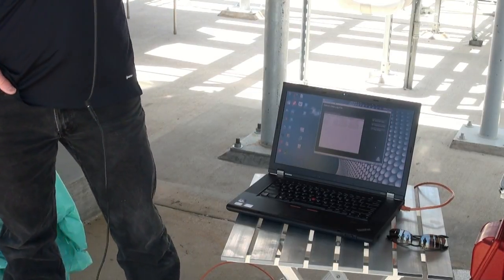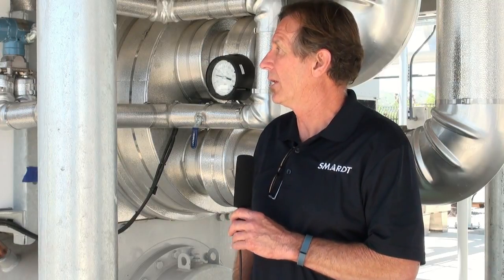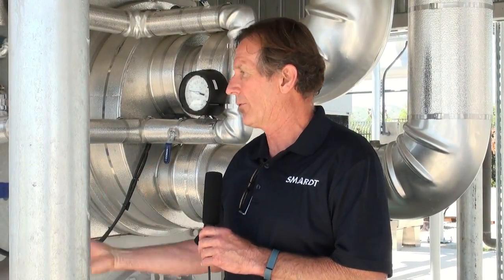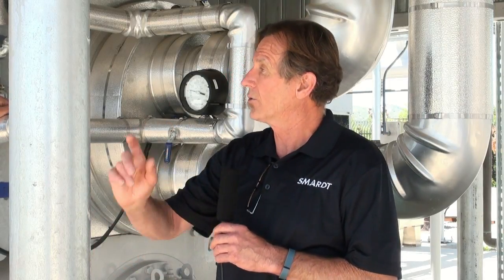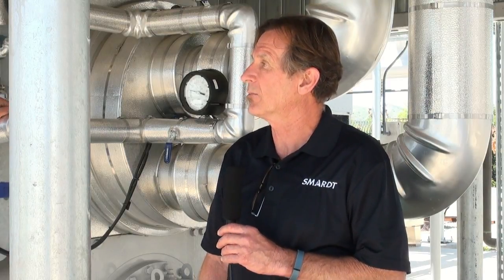Okay. Any other questions? How do you reset the alarm? Oh, okay. That's a good question. We didn't cover that at all. Typically, everything is set for automatic reset. So if you do suffer a fault, it will automatically recycle itself. It has a fault timer, which is about 180 seconds. So it'll run through that fault timer. Once that time's out, you go into a restart delay timer, which is about another 180 seconds, and then the machine will just automatically restart itself and take off, as long as all those LEDs are green in the system overview.